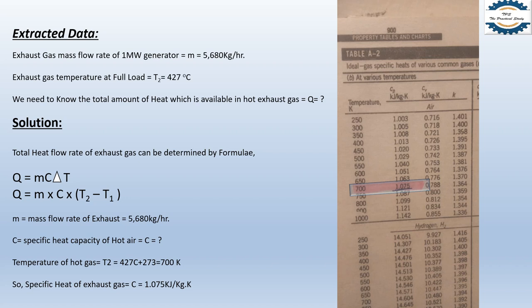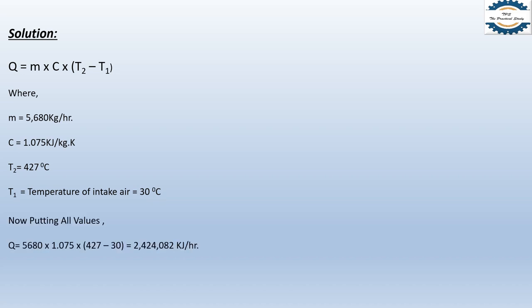We have mass flow rate m = 5680 kg per hour, specific heat capacity c = 1.075 kJ/kg·K from the thermodynamic chart, T2 = 427 degrees centigrade from the data sheet, and T1 = 30 degrees centigrade as the intake air temperature. You can substitute your own ambient temperature if it differs from 30 degrees centigrade. For this average calculation I am taking 30 degrees centigrade.